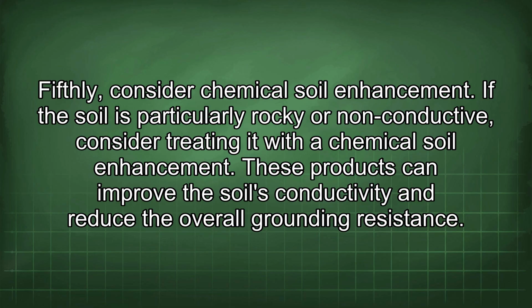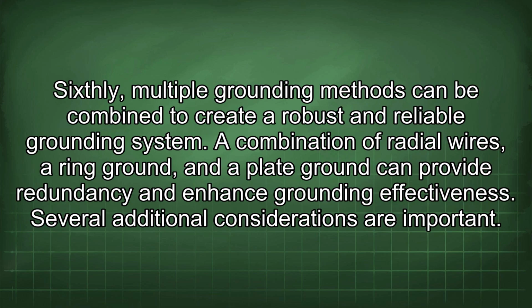Fifthly, consider chemical soil enhancement. If the soil is particularly rocky or non-conductive, consider treating it with a chemical soil enhancement. These products can improve the soil's conductivity and reduce the overall grounding resistance. Sixthly, multiple grounding methods can be combined to create a robust and reliable grounding system. A combination of radial wires, a ring ground, and a plate ground can provide redundancy and enhance grounding effectiveness.